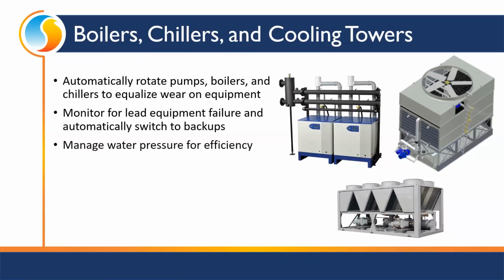We can manage water pressure within the system for efficiency. We do have multiple efficiency strategies to choose from, whether that is resetting the temperature on a hot water loop or resetting the supply air temperature. Okay, if it's not super hot outside, why do I need to send super cold air down the duct? Well, maybe I don't, and we can adjust that to maximize both comfort and efficiency.